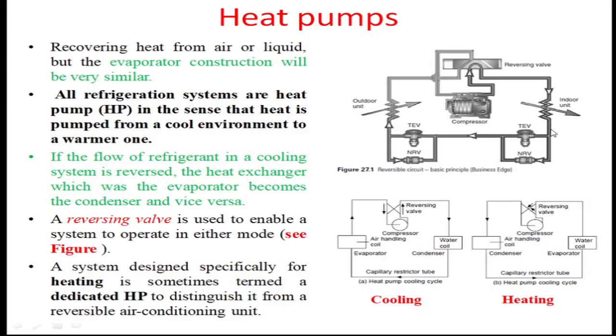After the indoor unit rejects its heat, the indoor unit serves as a condenser, condensing the refrigerant into high-pressure liquid near ambient temperature. The refrigerant then goes via the TEV to the outdoor unit — another heat exchanger — where it gains heat, becoming low-temperature, low-pressure vapor. It then goes via the reversing valve to the suction side of the compressor. In this case, the indoor unit supplies heat and the outdoor receives heat.